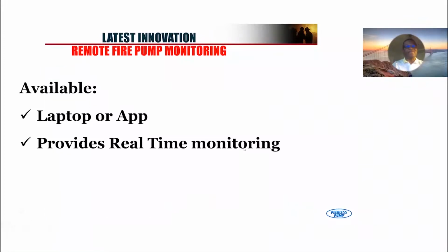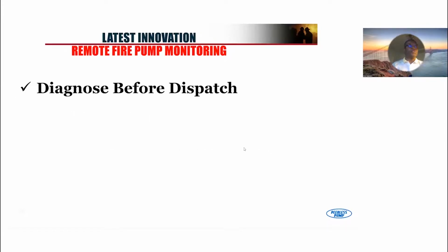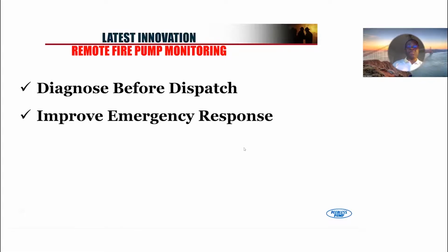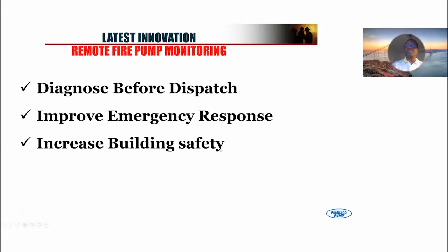This is something you can download on your app, or look at on your laptop or desktop, and it provides real-time monitoring of your fire pump every single millisecond of the day. You can basically know what's going on with your fire pump. The idea is you diagnose before you dispatch somebody to the site, and it improves the emergency response in case of a fire because you have all kinds of data. The pump can tell you a lot about what's going on, it increases building safety, and finally it gives you peace of mind.